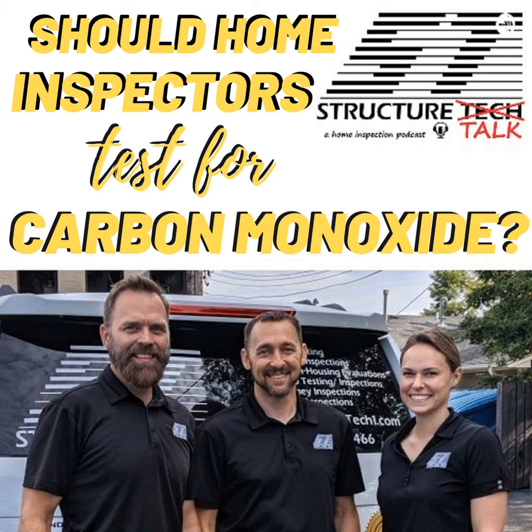Tessa, you're exactly right. It needs to get to steady state. I've heard some people say, well, you should only do a CO test after it's been running for 10 minutes or 15 minutes or whatever. And you're making stuff up. It's not about how long the furnace has been running. It's about it getting to steady state, and that means the flue temp is not rising. The exhaust gases are going to keep getting warmer and warmer, and eventually that temperature is going to plateau. It's going to stop rising. Once it stops rising, that's where you do your test.